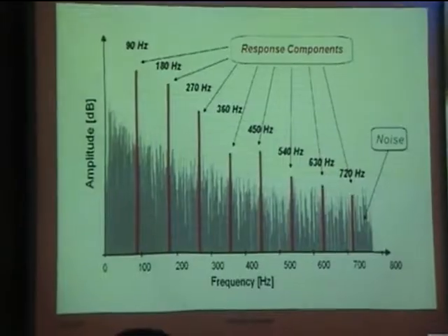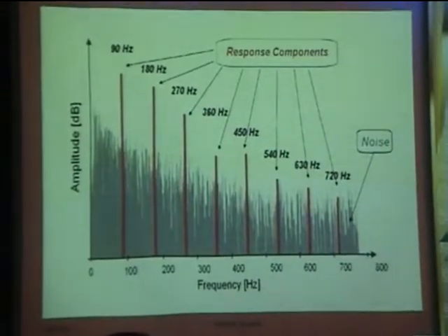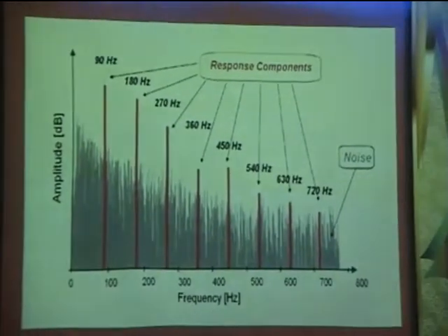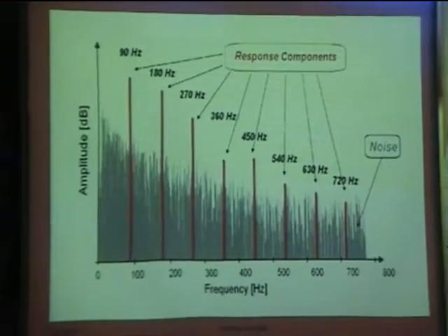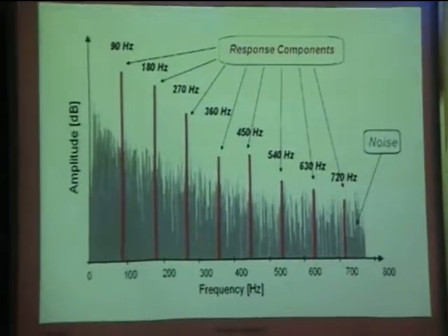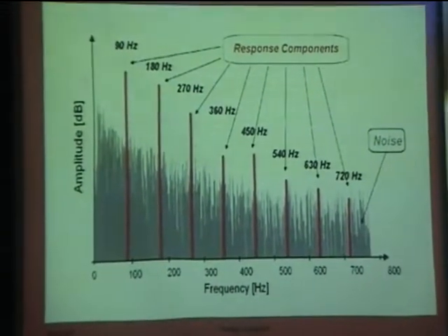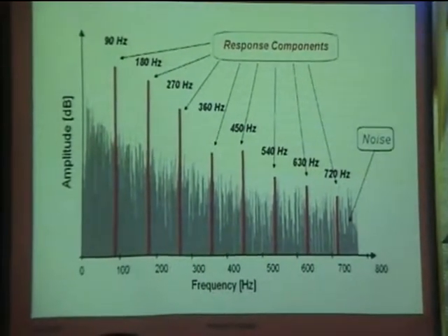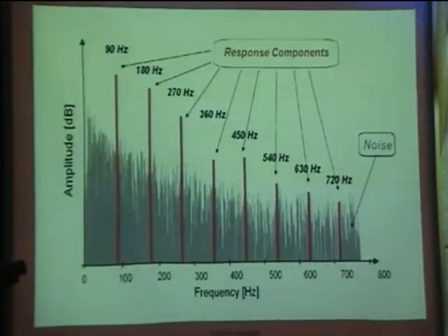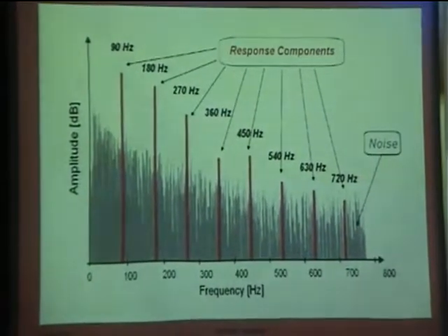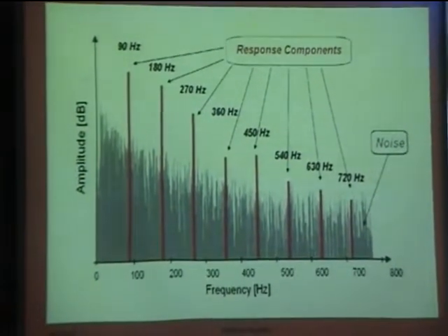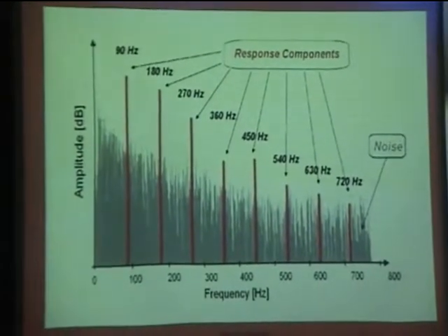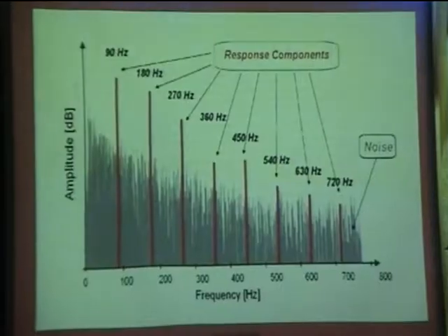And another thing which I don't know whether it's a positive thing or a negative thing, depends on how we take it, is that we do not see any response waveform but rather the algorithms are present within the computer, and we directly get a response in terms of whether the response is present or absent. Of course, sometimes we would be more confident when we see a waveform to make a judgment, but most often for screening purposes, this becomes pretty convenient when we have a direct answer whether the child can hear or cannot hear. We don't have to look for a waveform.